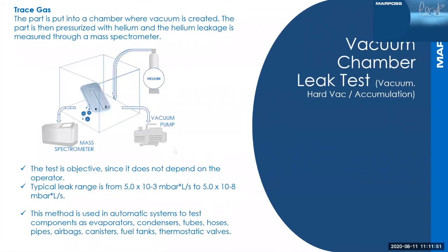Getting to our first trace gas system, the one everybody thinks of usually is a vacuum chamber leak test. This is the most common test method. Basically, the part is put into a test chamber. The part is pressurized with helium, and a vacuum is drawn on the chamber to try and pull out any helium through the test part. This is normally what we refer to as a hard vac system. A lot of times you'll start hearing people call a mass spec system a vacuum system. This sometimes gets confused with vacuum decay leak test systems, but there's a big, dramatic difference. The vacuum is a lot lower level than what you'll see on a vacuum decay system for mass spectrometer.